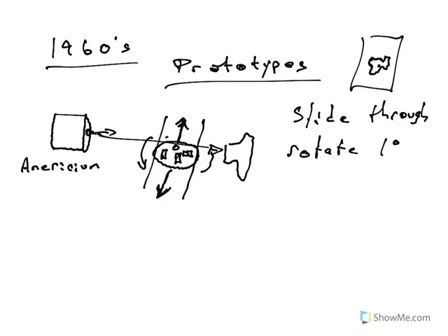And you keep doing it until you've rotated a full 180 degrees. So by the time you're done, this back material is now in the front, and the front material is now in the back. You've gone all the way around this object, and the whole time this detector is picking up how much X-ray is being attenuated, how much is being sent through.